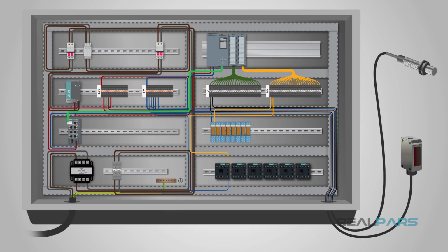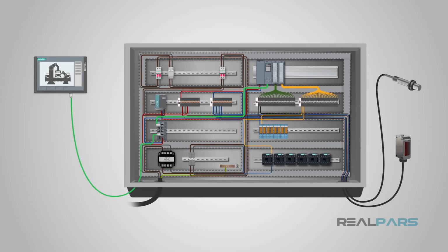We will also have a network switch located somewhere near the PLC. This will be powered with 24 volts, and it will be the hub for our communication to and from the PLC to network-compatible devices on the assembly line. One of those devices is our Human-Machine Interface, or HMI. An HMI can be mounted locally onto a panel door or in a remote panel located closer to the machinery. The HMI can be a very dynamic tool in assisting the operator in controlling and monitoring the machinery. The PLC will pass signals over the network to the HMI for monitoring, and the HMI can send signals to the PLC for controlling the machinery.